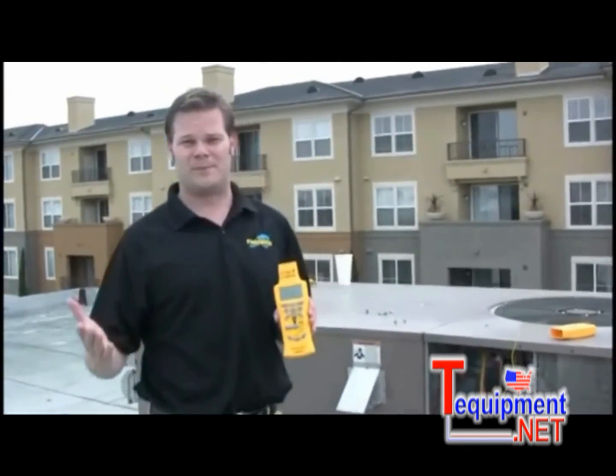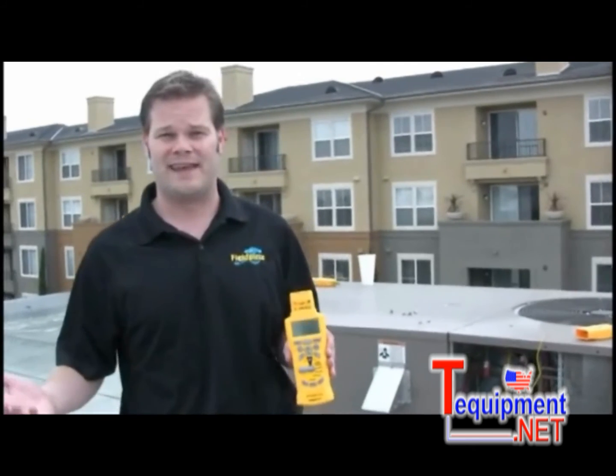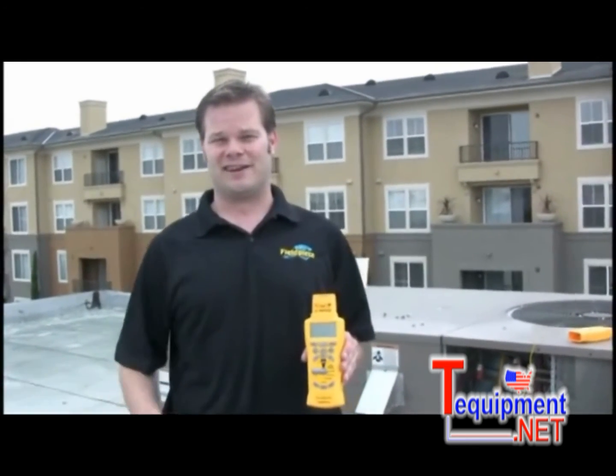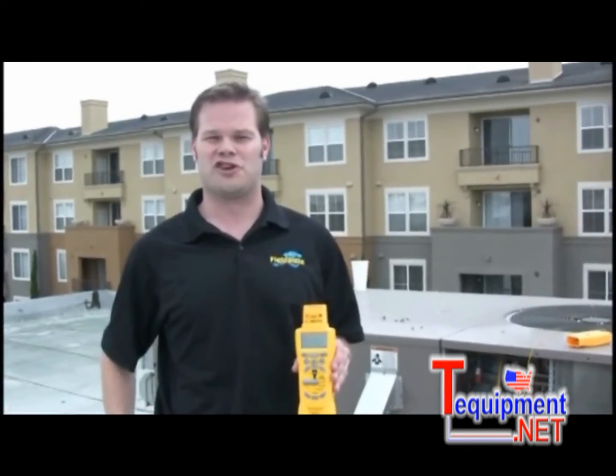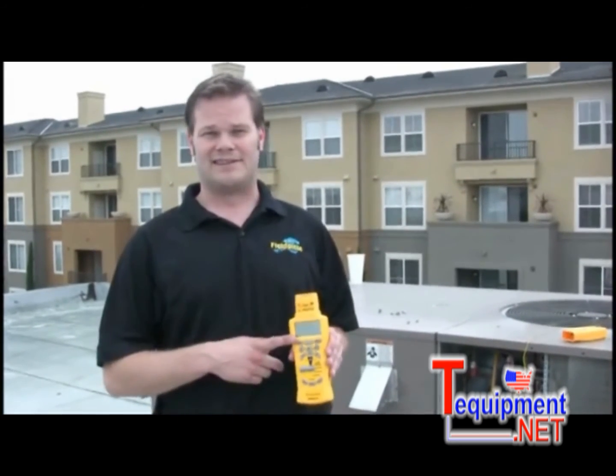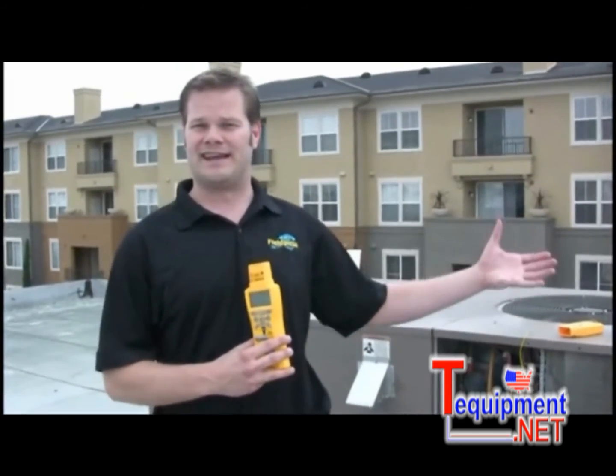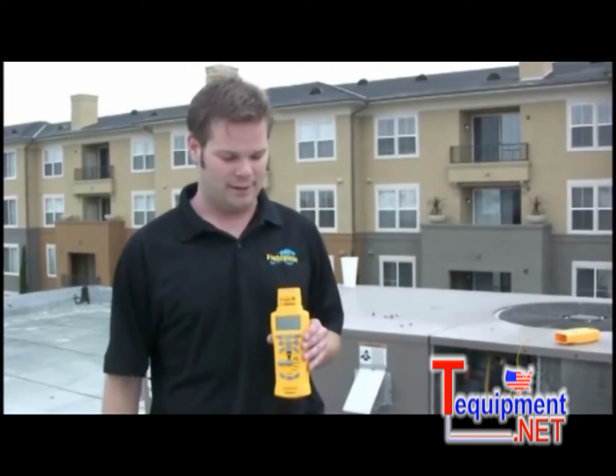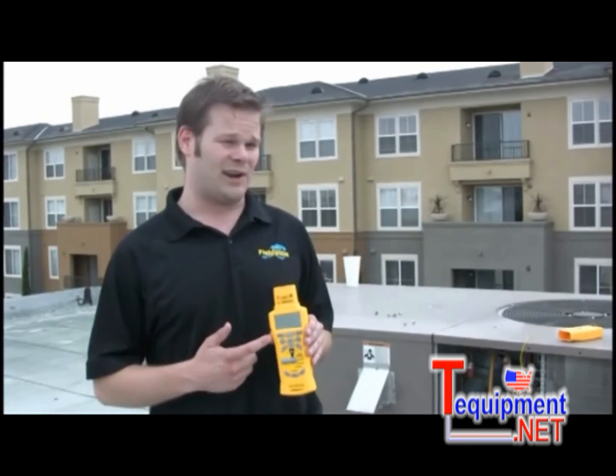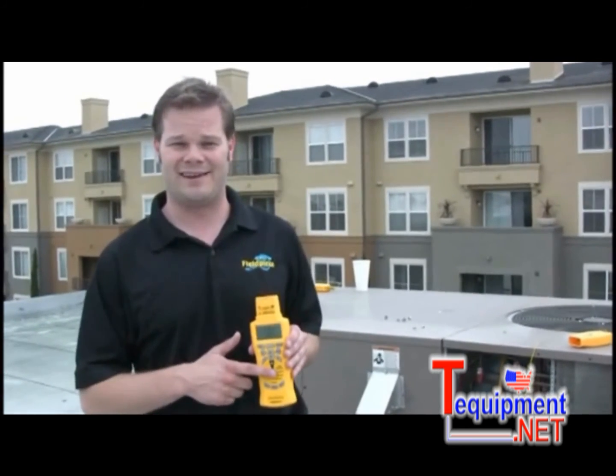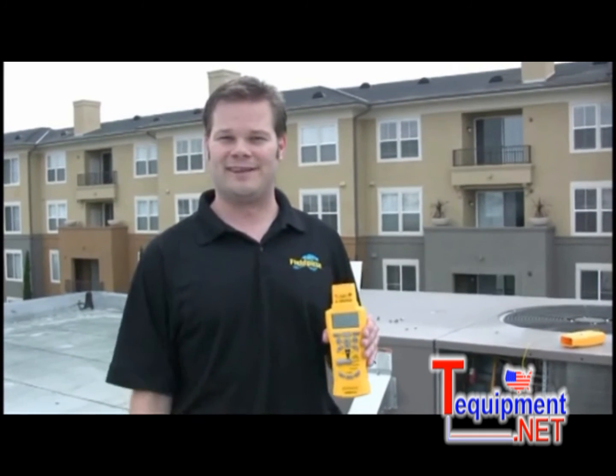We can validate our work, hand it back to our customer, tell them that we do have to add refrigerant, and then he's going to understand why we're charging him for refrigerant. After we're done adding refrigerant, we can take a retest and have a before and after. And that's basically how the HVAC Guide works for all 4 of the tests that are on the dial. And we just did superheat with the HVAC Guide.